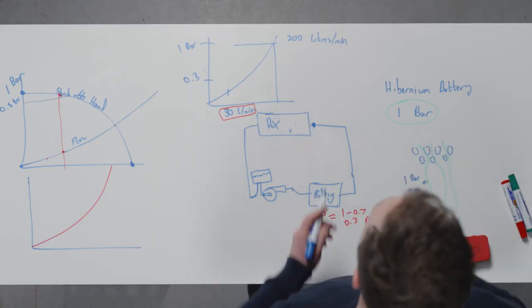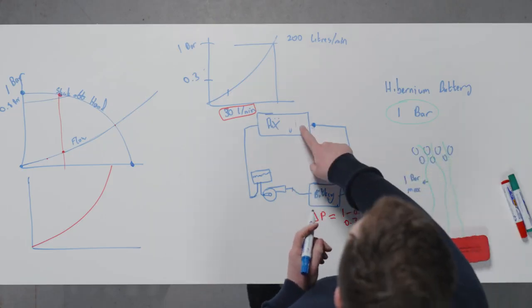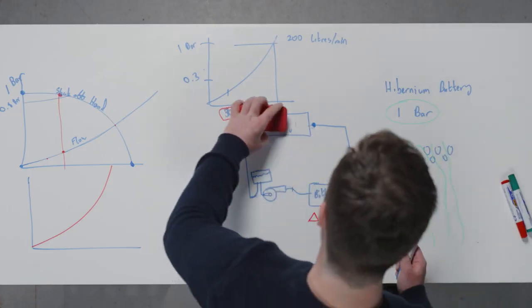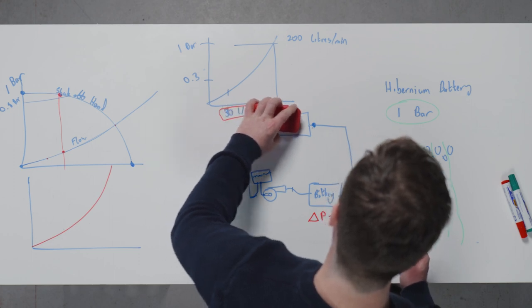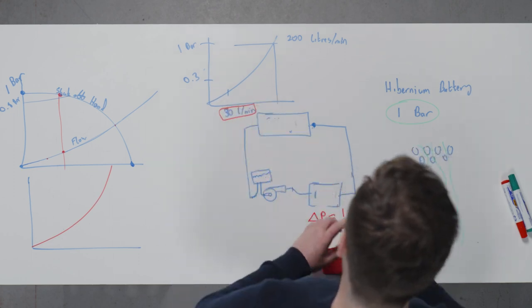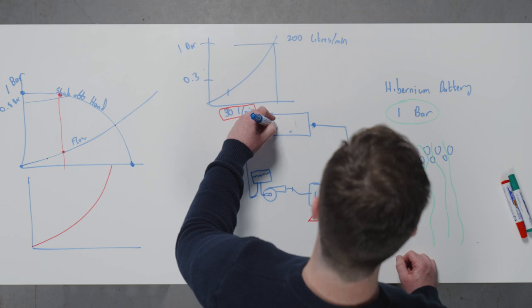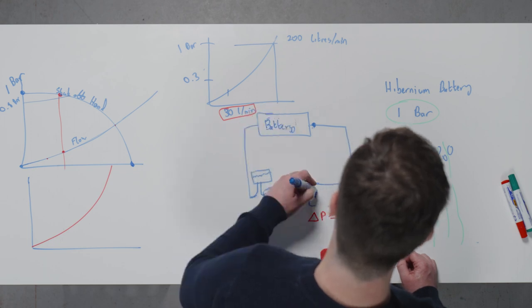So one final component we want to add into our system is ensuring that you don't have any overpressure events. So we always recommend that every battery cooling system has a pressure relief valve installed before the pack. So back in our original configuration here of a battery and our heat exchanger, the battery's been put in the optimum location.